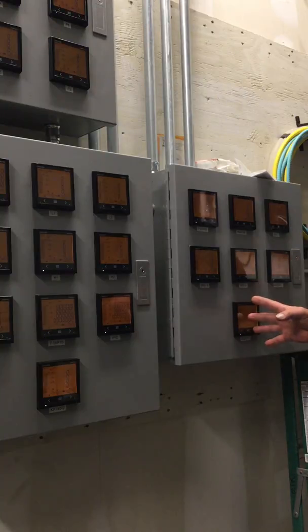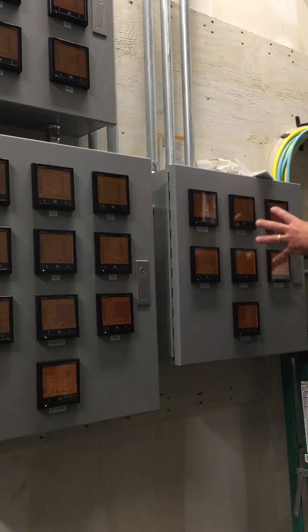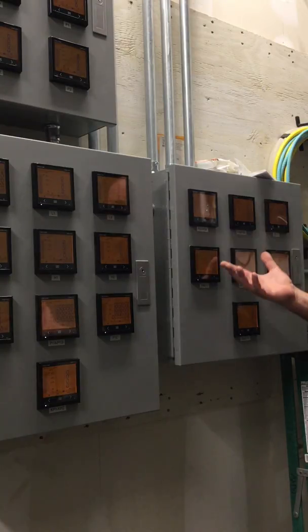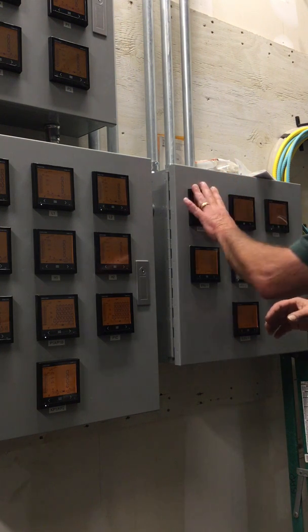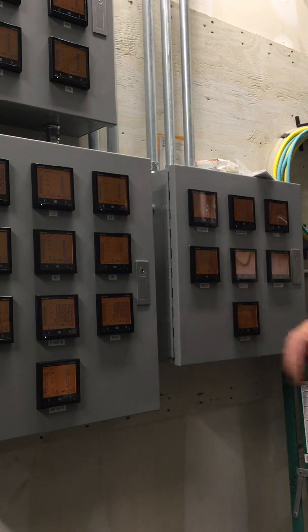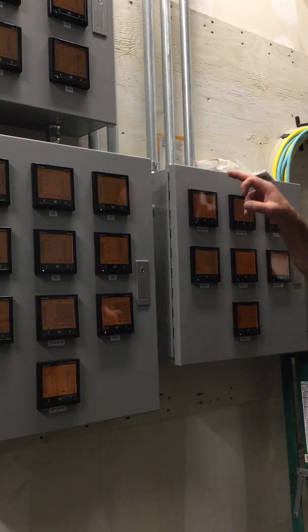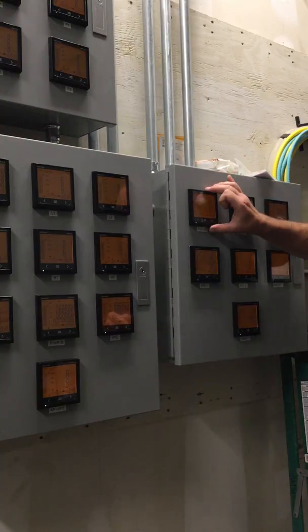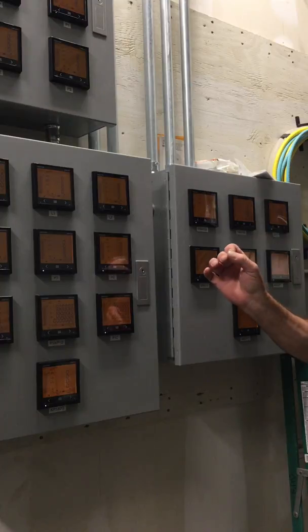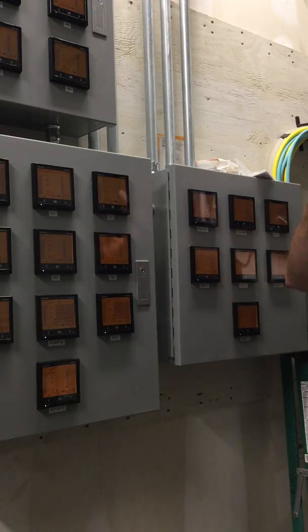The information that's displayed on the meters, depending on what's being pulled by the BAS, it's either mirroring the meters or sections of the meters. I just don't know what they have displayed at their head end, okay? The meter is a microprocessor-based meter. It does the thinking. It has firmware. Inside the meter is also a RAM memory chip. There's no batteries for memory in the meter. Every 2 seconds, the processor compares the active piece of firmware to the firmware that's in the RAM memory chip. It does a check and says, okay, I'm still thinking correctly.